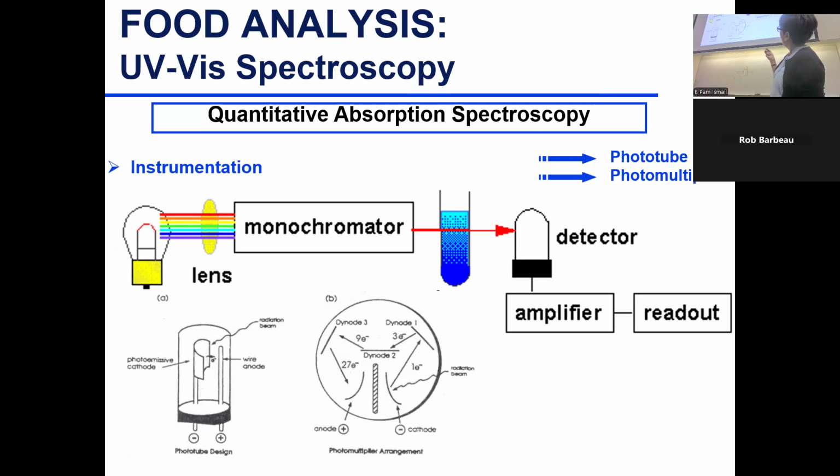So you have the light that reaches the detector, hits a cathode, an electron gets transmitted, it goes to a dynode and then multiplies. And it keeps multiplying until you have it multiplied quite a bit and enhance the signal and therefore enhance sensitivity.